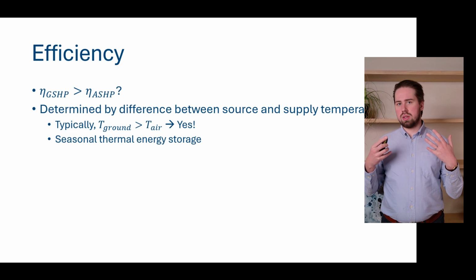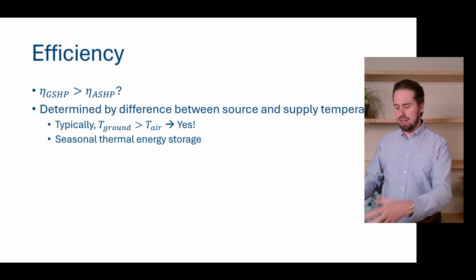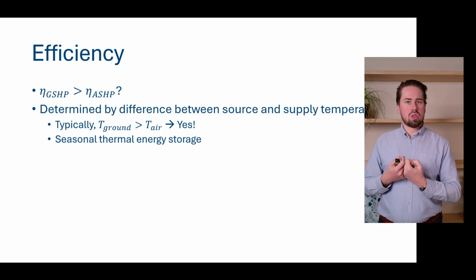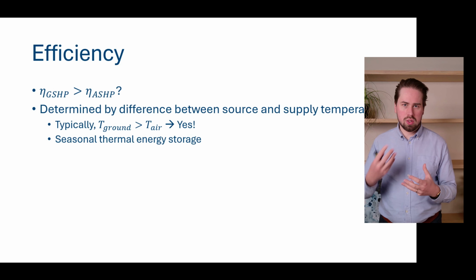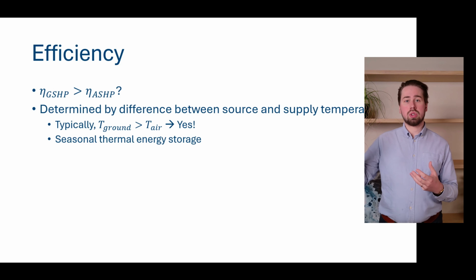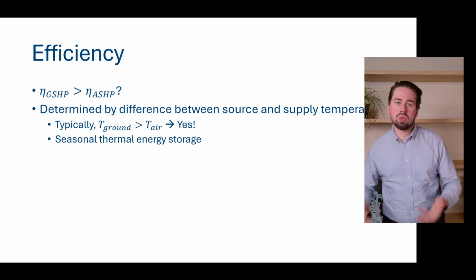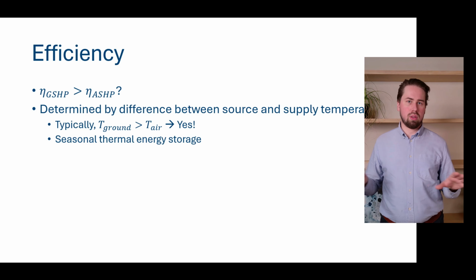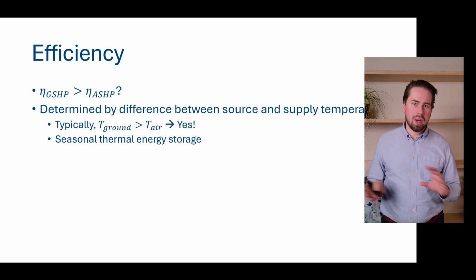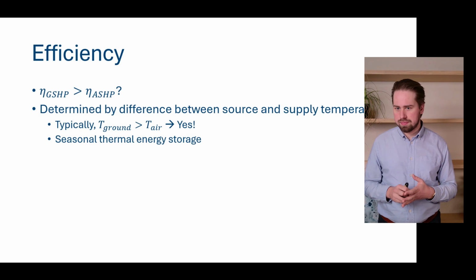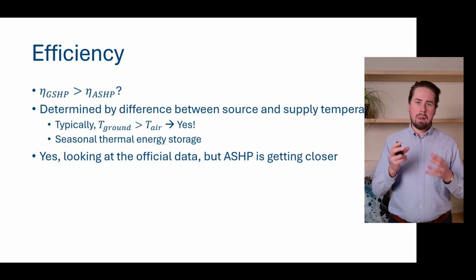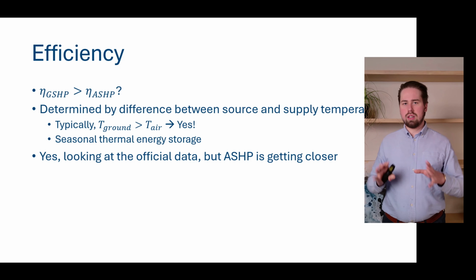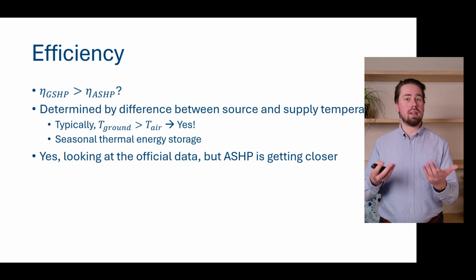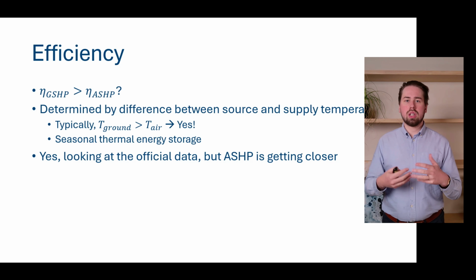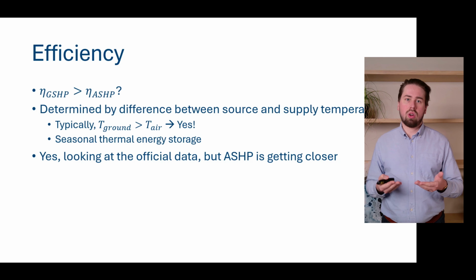That's also because ground source heat pumps are not just taking energy out of the ground, it's also seasonal thermal energy storage. Typically in summer, we're also injecting heat back into the ground in order to keep the ground temperature more or less level. We will cover that in way more detail throughout the rest of the course. But the problem is that, yes, if you look at the official data, ground source heat pumps were historically way better than air source heat pumps. But the technology of air source heat pumps also evolved, and now on paper they're more or less the same.